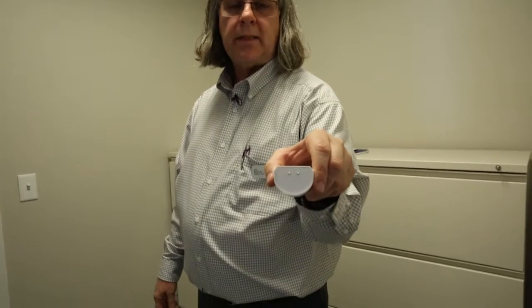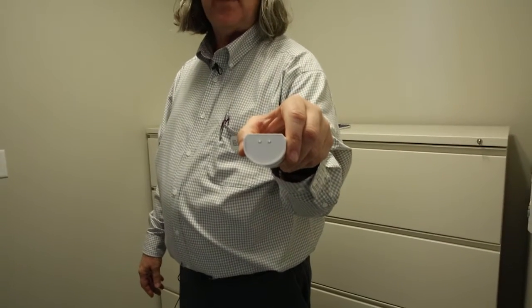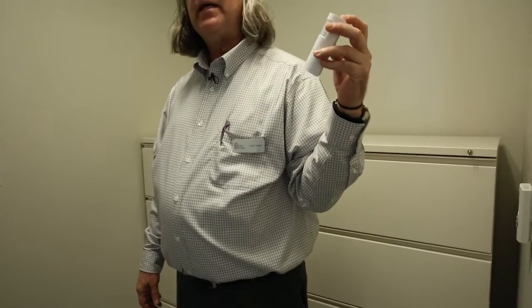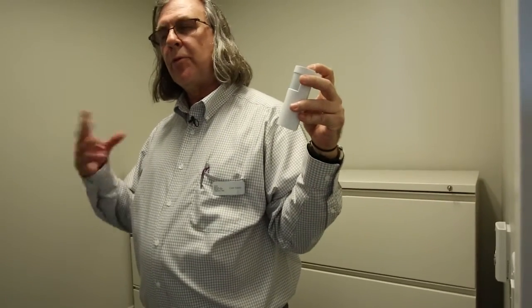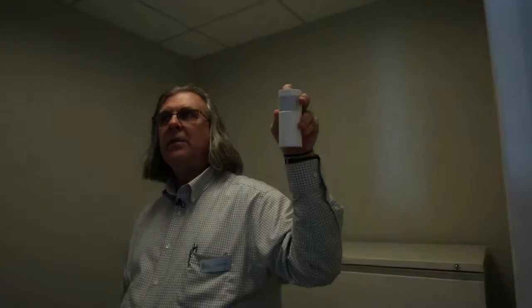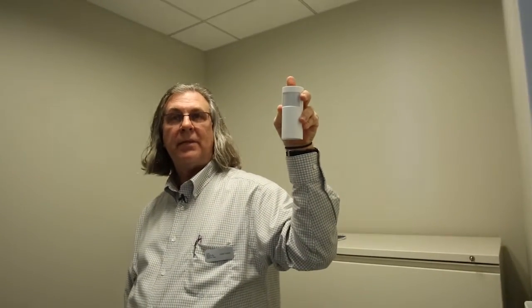There are 2 buttons at the top. One has a light bulb on it, the other says test. With the light bulb one, we can simulate whether the room is occupied or not. The first time I press it, see how the orange light goes on? It's as if I walked in and it detected me. There was no change because the lights are already on. But when I press it the second time, it simulates unoccupied and the lights go off. So you can use this to test it.